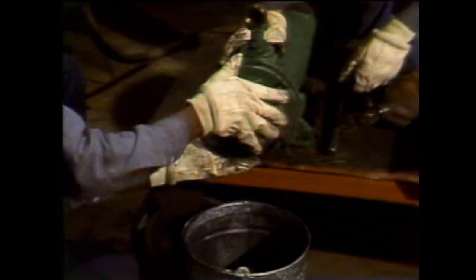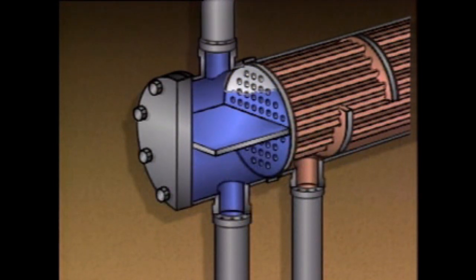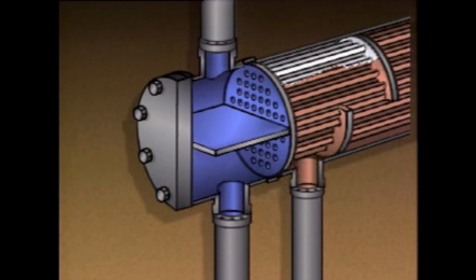When air, non-condensable gases, or other vapors are trapped inside a heat exchanger, they can prevent the unit from operating efficiently. This is because the air or gas can either blanket the tubes or block the tubes off and prevent fluid from flowing through them. Gas trapped on the tube side can block off tubes and prevent fluid from passing through them. Gas trapped on the shell side can displace the shell side fluid at the top of the heat exchanger, reducing the amount of tube surface area exposed to the shell side fluid and thus reducing the amount of heat that can be transferred.